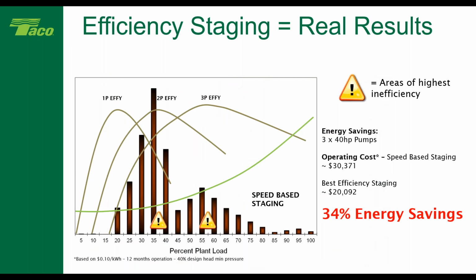So a real world example, 3 x 40 horsepower pumps. This building was done with self-sensing, with parallel and control and efficiency-based staging. It was run for the first year in straight speed-based staging. Their operating cost was over $30,000 per year just for the pumps. The second year, they turned speed-based staging off and turned best efficiency staging on. They dropped their pump operating cost by over $10,000.